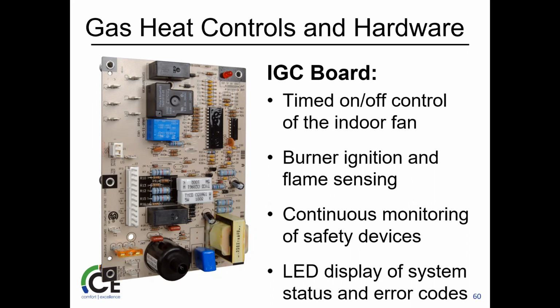Monitors safety devices the whole time. So even though you're running for a bit and then maybe that flame sensor loses it, that way it's going to shut down. So it watches that constantly. It's not just a startup like some of the old boards used to be. Obviously, and then of course error codes, right? We're going to have that little blinky light on this one. It's going to tell us at least what sort of kind of happened.